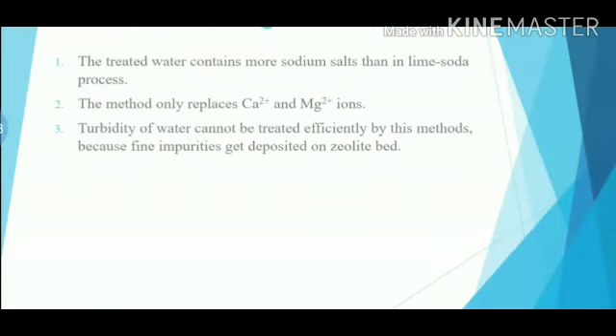Now, disadvantages of process. The treated water contains more sodium salts than in lime-soda process. The method only replaces calcium and magnesium ions. Turbidity of water cannot be treated efficiently by these methods because fine impurities get deposited on zeolite bed. Thank you.